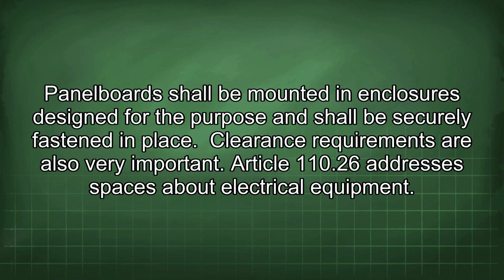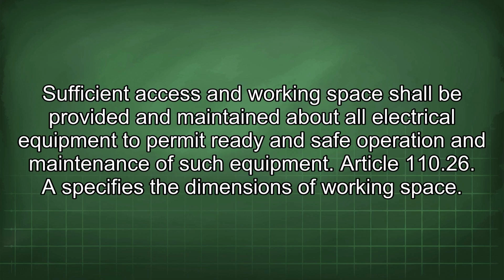Clearance requirements are also very important. Article 110.26 addresses spaces about electrical equipment. Sufficient access and working space shall be provided and maintained about all electrical equipment to permit ready and safe operation and maintenance of such equipment. Article 110.26(A) specifies the dimensions of working space.